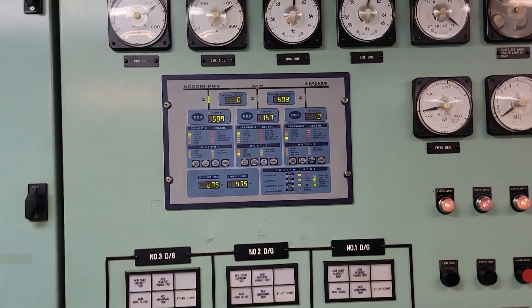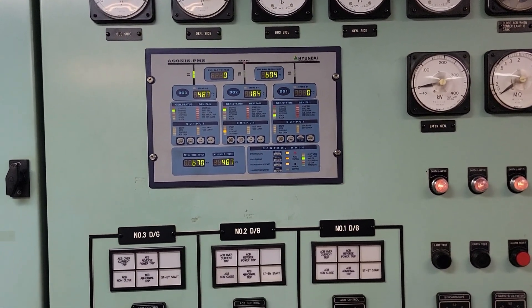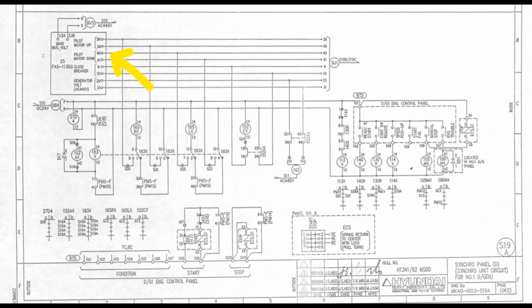After analyzing what is happening, we concluded that due to the fact that the ACB closed signal disappears, the power management system thinks the generators are not synchronized and starts the synchronization process again by connecting a synchronization relay, which tries to synchronize the generators already operating in parallel mode. Because the measuring inputs of the synchronization relay receive the same voltage phase angle shift signals, the relay tries to increase the RPM of the generator that needs to be synchronized with the bus bars. The voltage phase shift angle remains the same and the RPM of diesel generator number two begins to gradually increase, taking all the load.